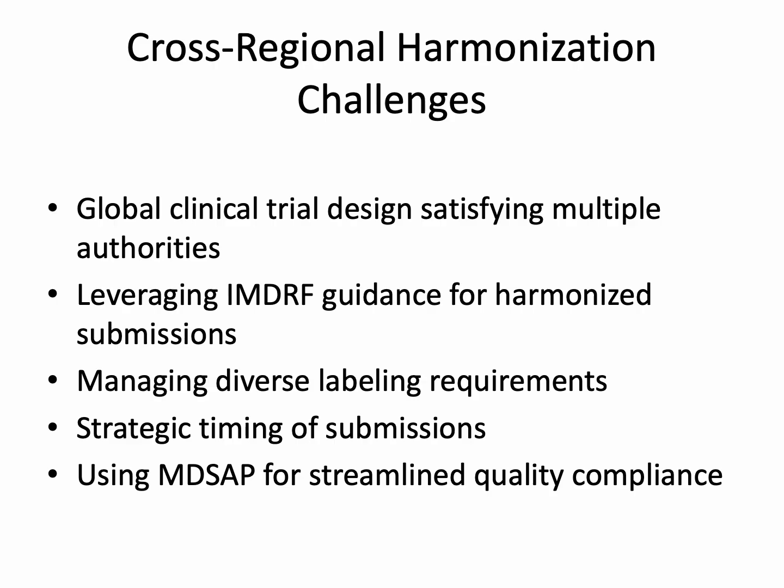Participation in MDSAP enables a single audit to meet quality system requirements for multiple jurisdictions, reducing redundant inspections and ensuring consistent compliance globally. This approach illustrates the importance of integrated planning, harmonization, and proactive communication with multiple regulatory authorities.